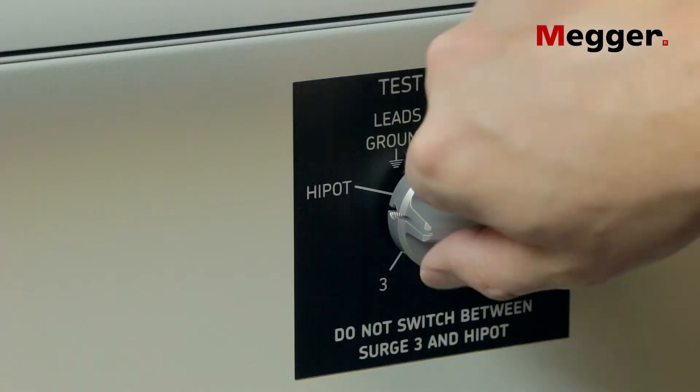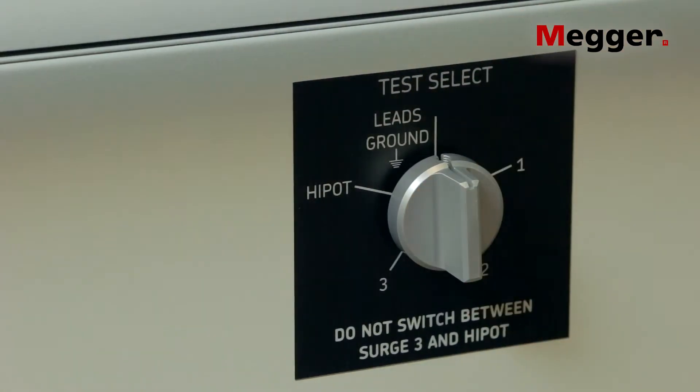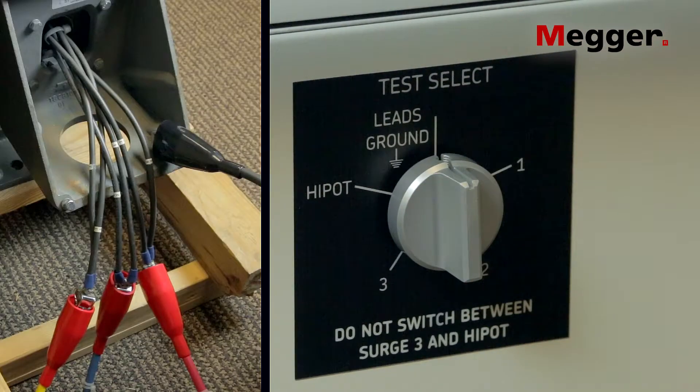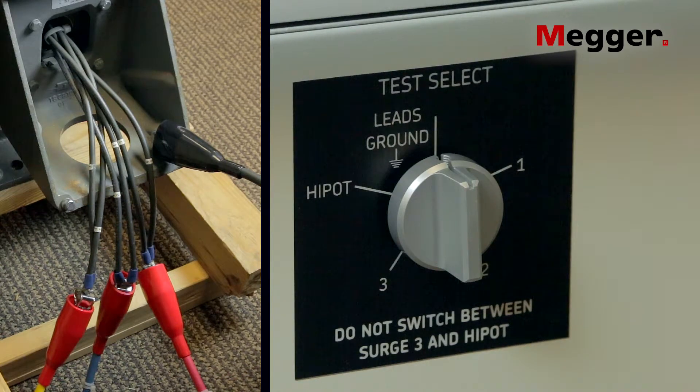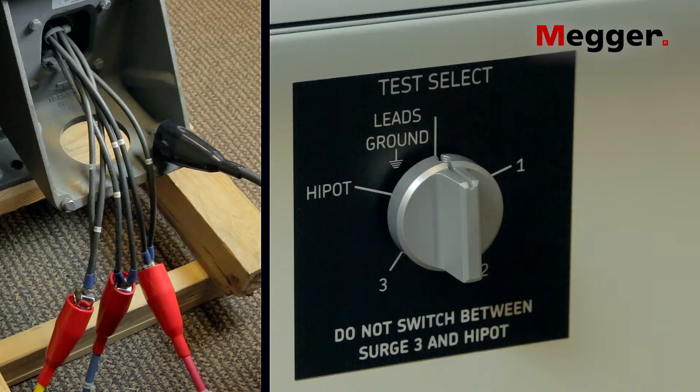Turn the test select knob to the lead's ground position. The DX will remind you to do this. To ensure the test circuit is adequately discharged, maintain the ground connection after testing for the same duration as the high voltage was applied.